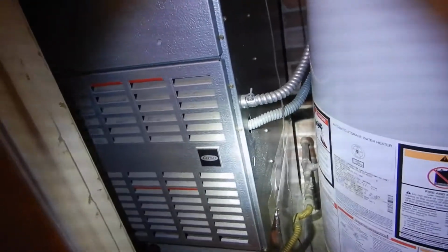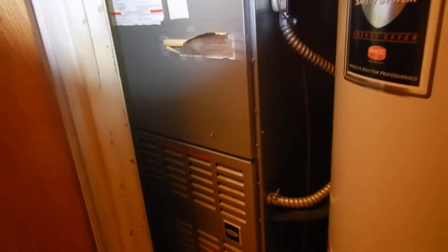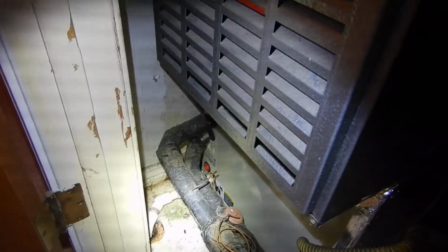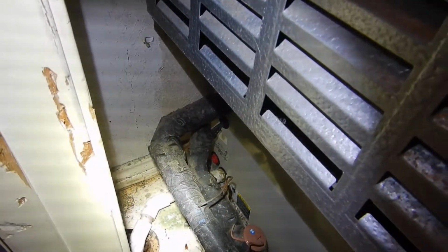We learned we don't have a care and use manual. We learned that our attic ventilation is suspect. Our mechanical closet ventilation, including the attic makeup air, is suspect. We learned that we've got an obsolete gray gas supply line that's improperly entering the cabinet. We learned that we do not have sufficient service access in front of the indoor air handler. In fact, if you wanted to replace this, you would have to remove the water heater. We learned that our evaporator coil drain line is clogged. It does not have a P-trap. It's not insulated. We do not have a safety switch.